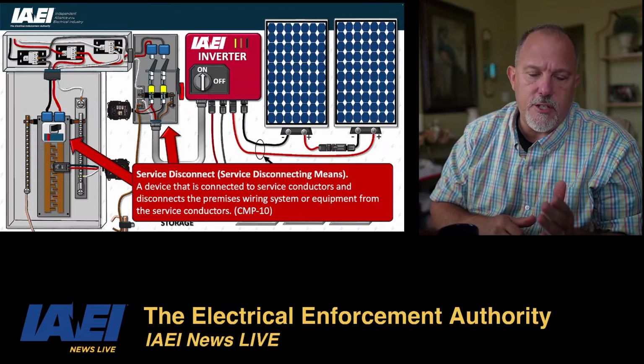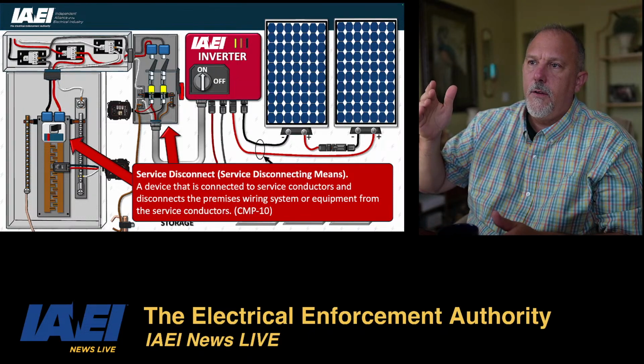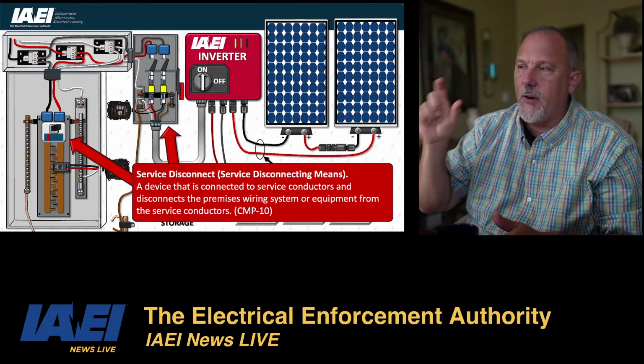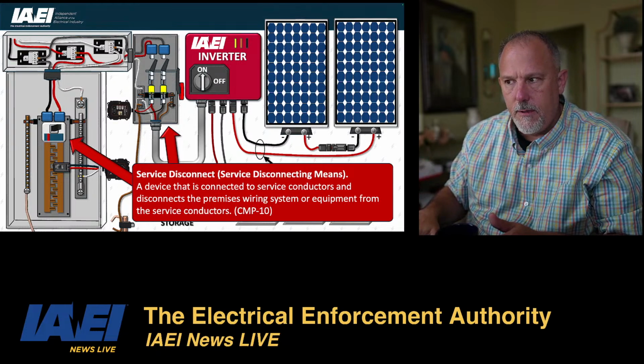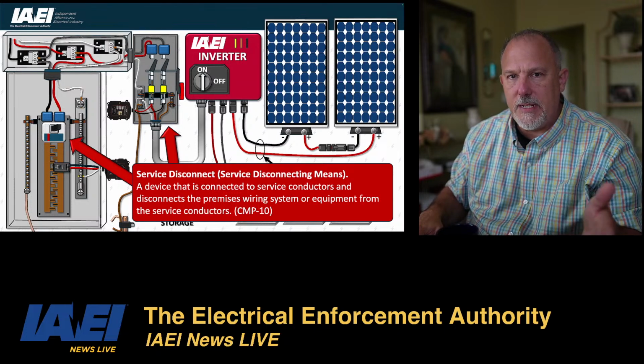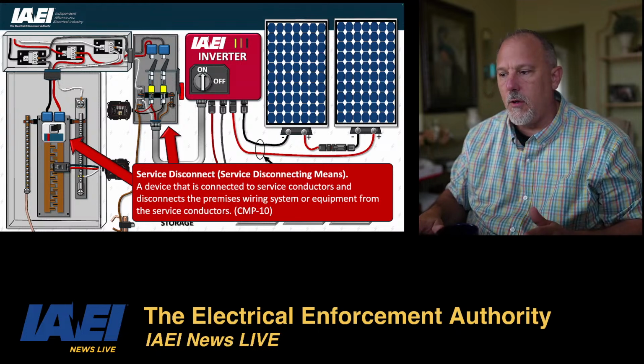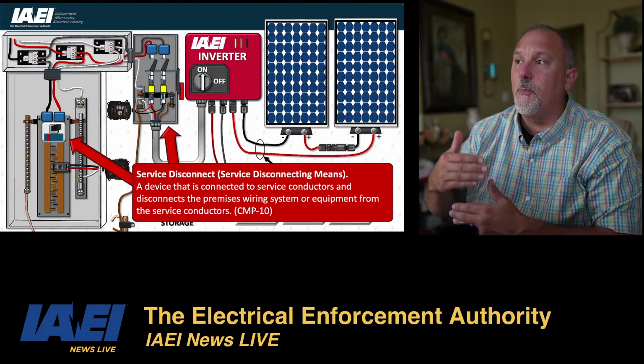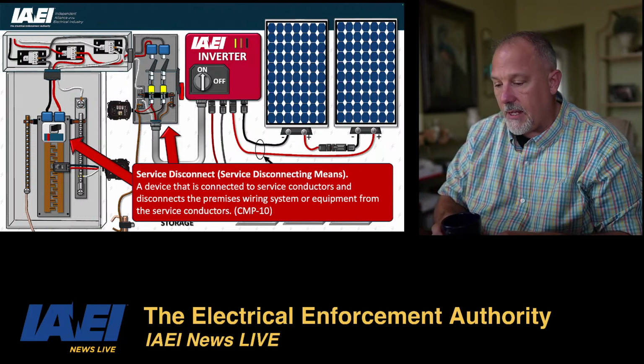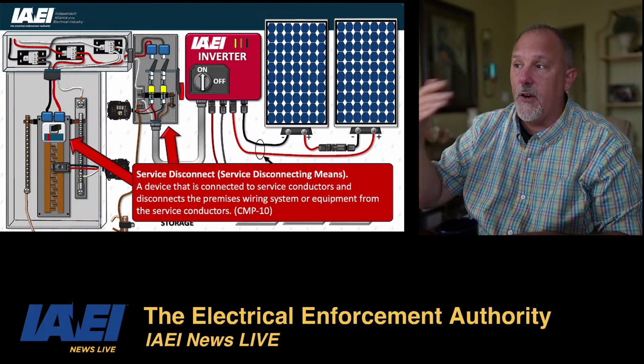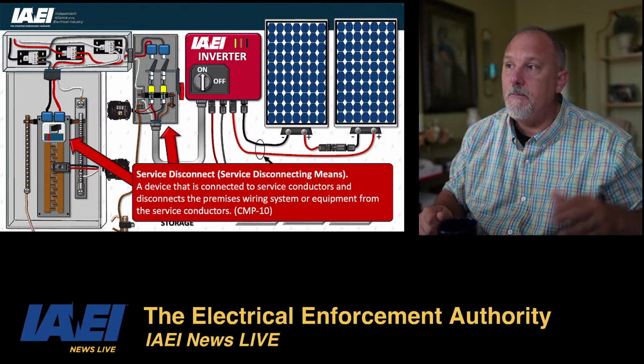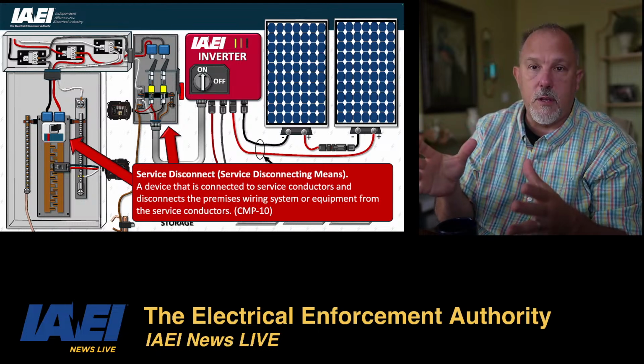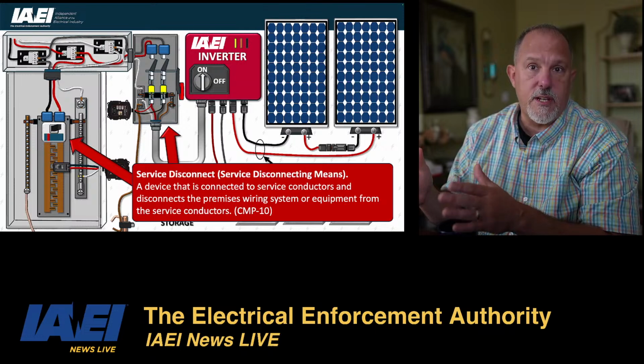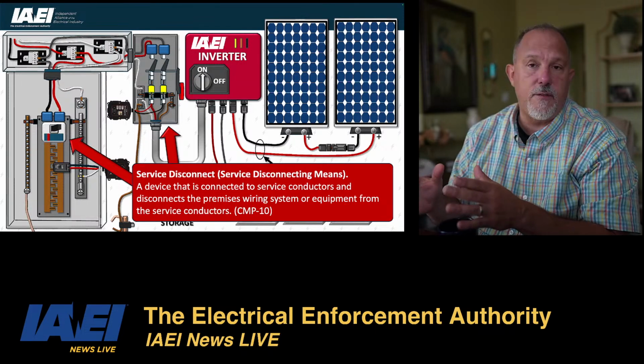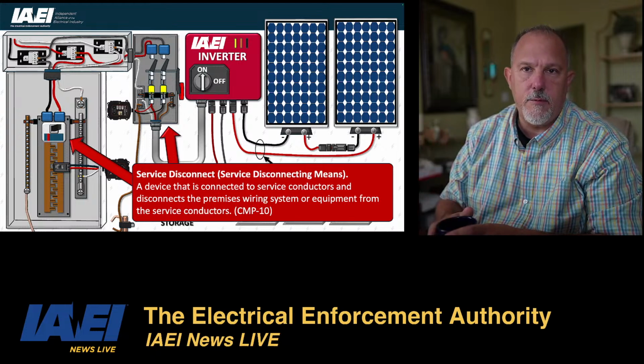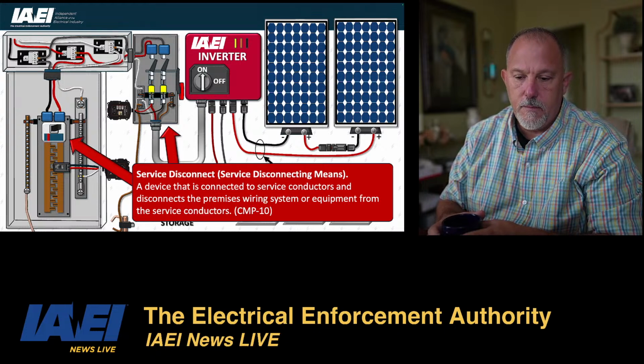The thing you've got to remember is this equipment will be listed, like the inverter is listed to UL 1741, which is designed and built in combination with other IEEE standards and with an eye on the utility for utility interactive use. So you'll see a lot of utility engagement in the product standards, so that when an inverter is made, it's made with an eye on the utility. And from an installation perspective, utilities are all over Article 230, that's service equipment. And they should be all over Article 705 as well. In fact, I think the stimulus for Article 705 came from an IEEE document that was heavily driven by the utility industry.